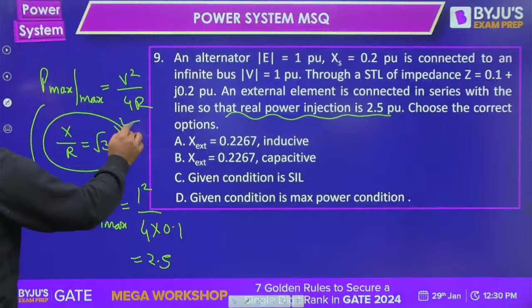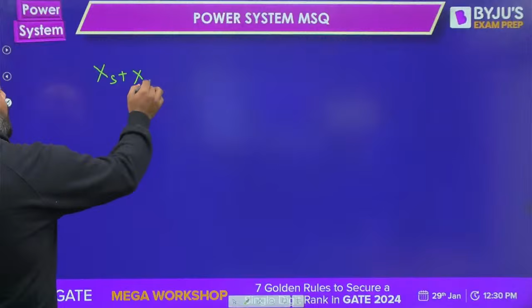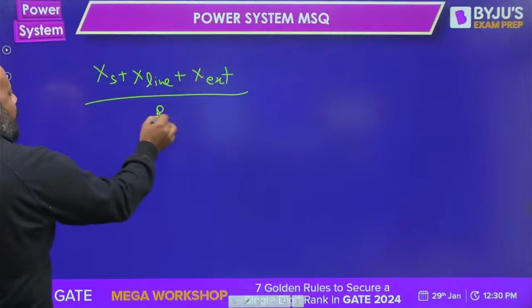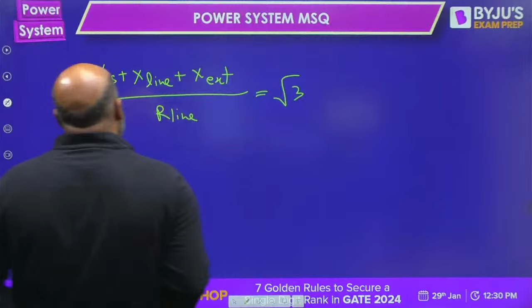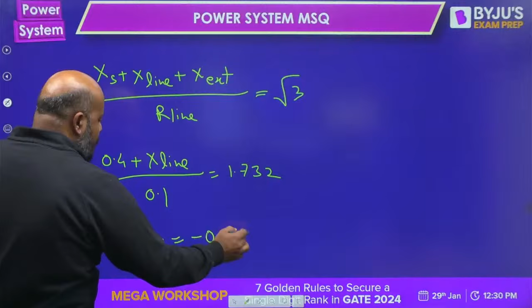But here it is XS plus the synchronous reactance X, and the short transmission line X is 0.2. So this is X line plus the external element you are adding, divided by R line, and this should equal under root 3. This is 0.4 plus X line divided by 0.1, equals 1.732, so X line comes out to minus 0.2267 per unit.